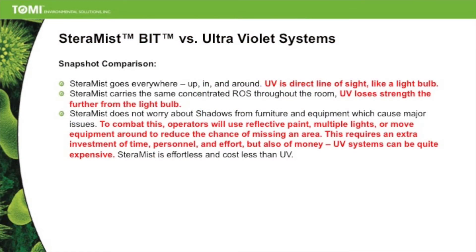Comparing the SteraMist fogging solution versus ultraviolet systems: the SteraMist is a fog and it's going to go everywhere. The UV is a direct line of sight, like a light bulb. The farther away you are from the UVC system, the less kill you're going to get. The beauty of using either the surface unit or the environmental system is that you get an even distribution of OH ions. You don't have to worry about shadowing, getting underneath something, or getting into drawers. The fogging technologies allow for better distribution than a UVC system.